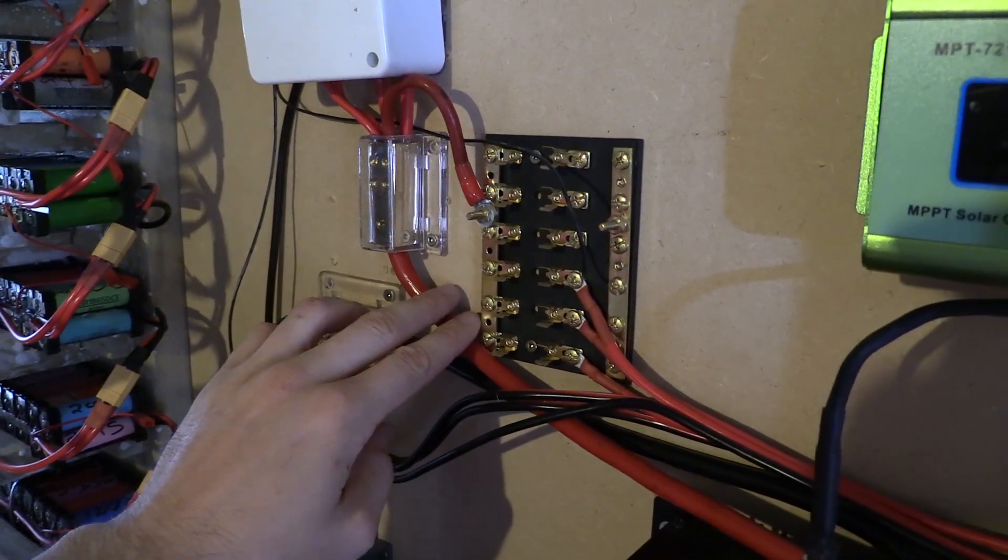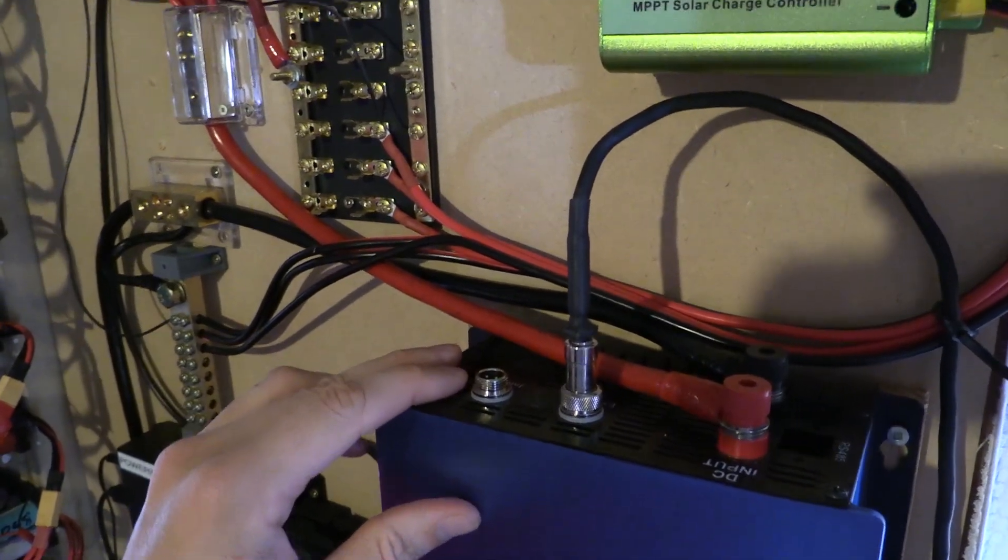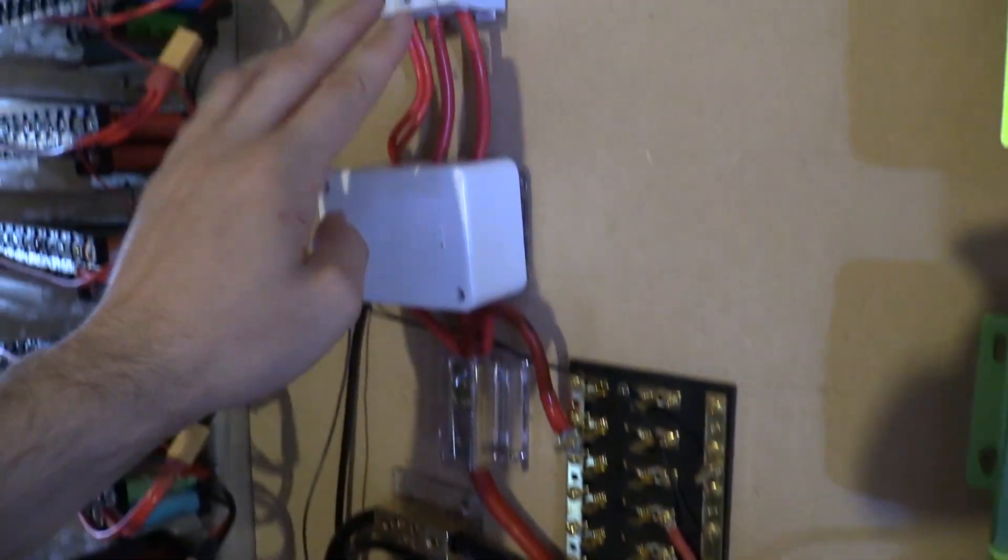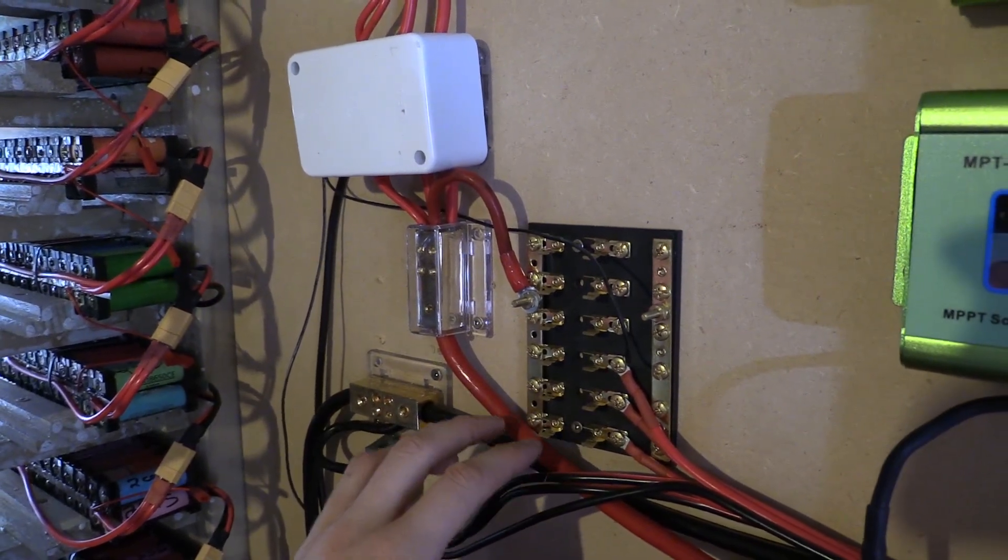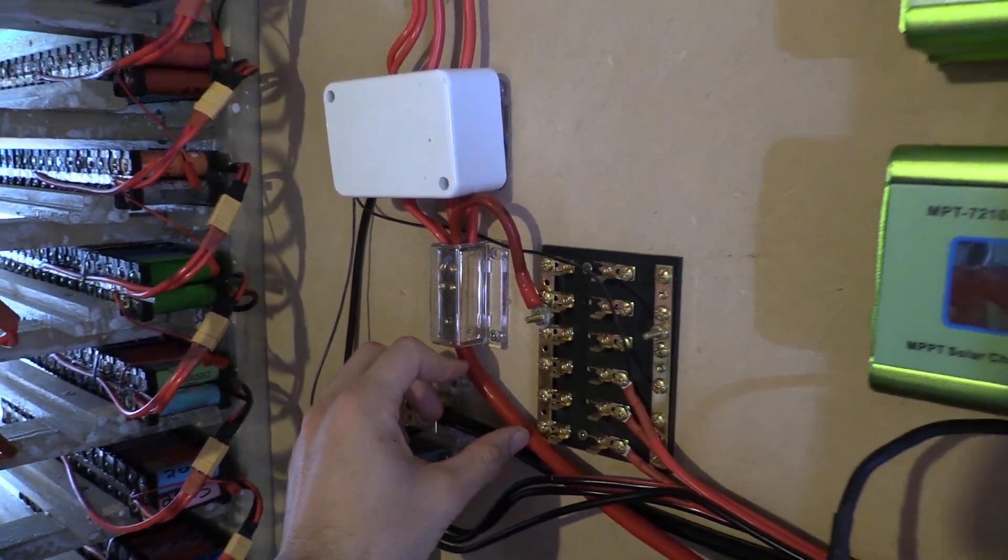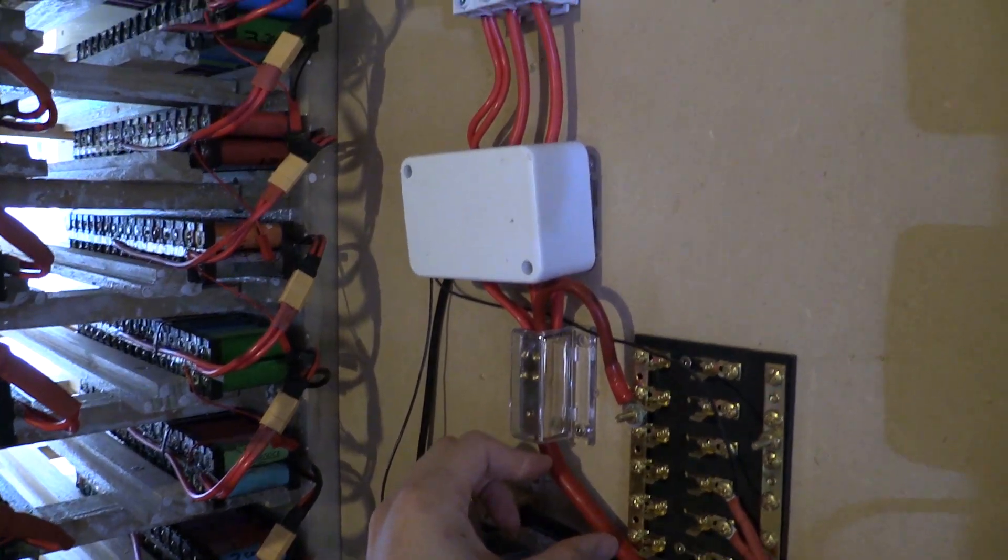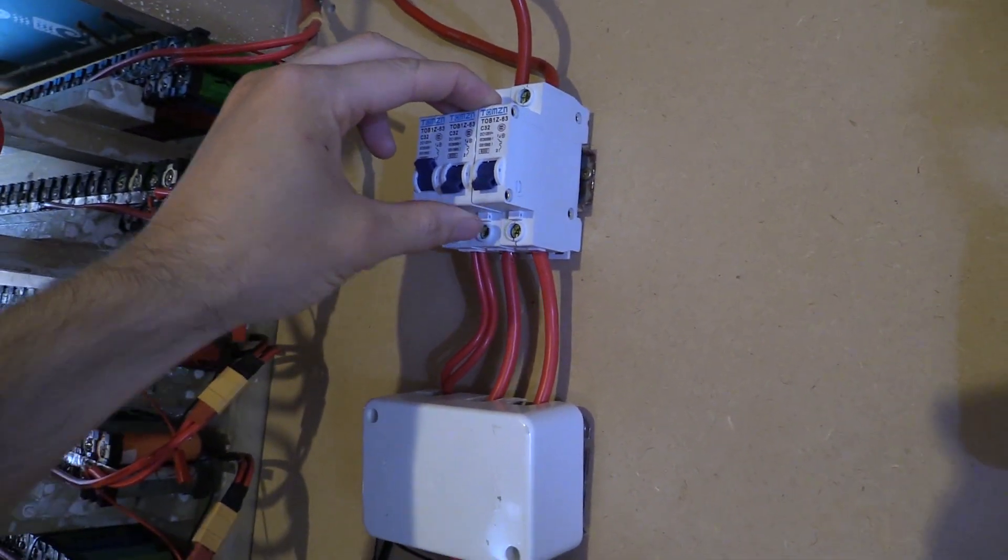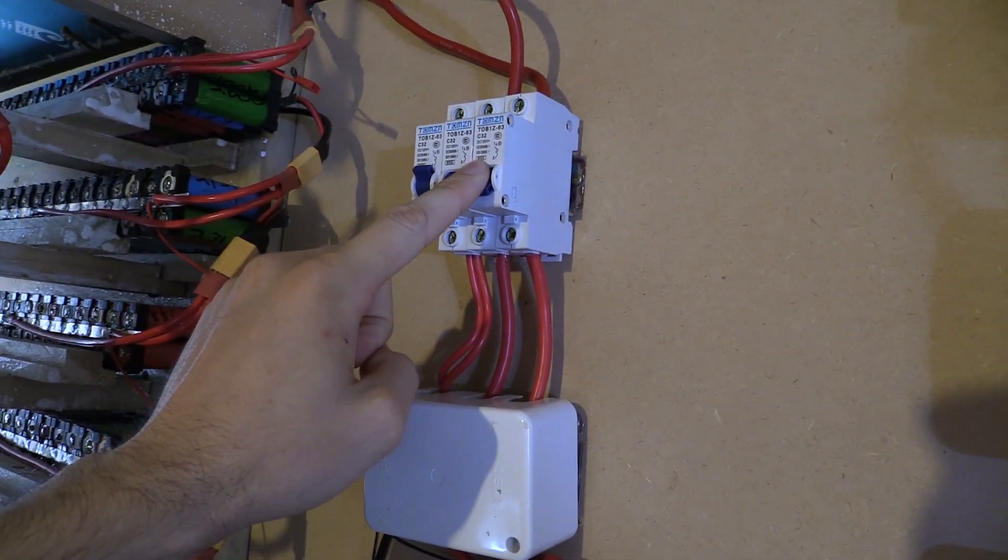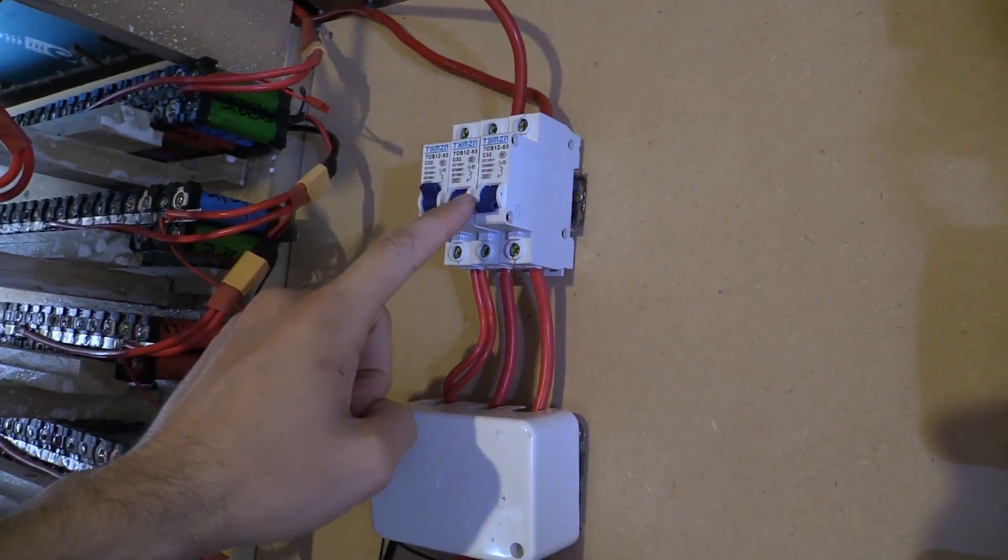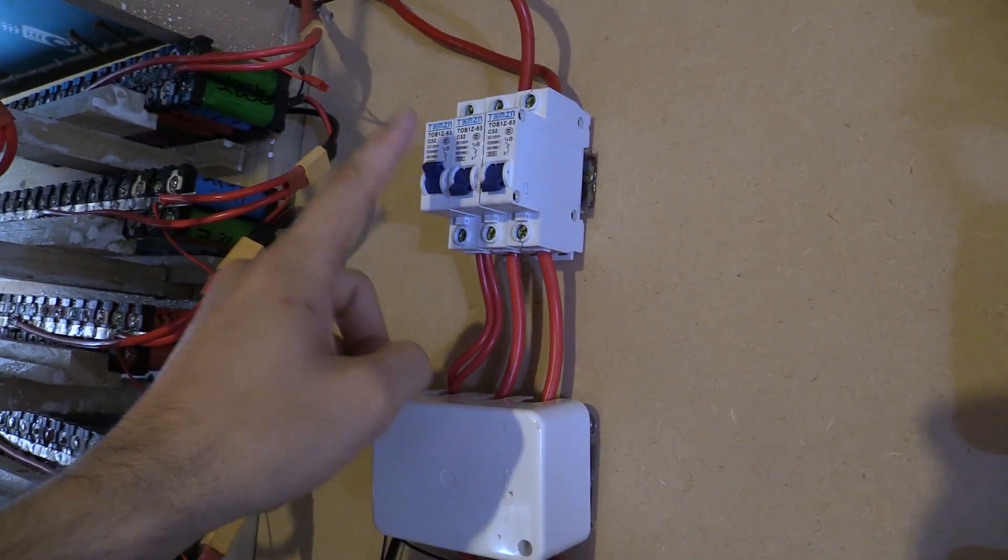What I possibly should have had was a 32, or maybe this pulls 32 amps, so potentially I should have had a 40 amp fuse or breaker on the feed into the inverter. That way that's the thing that would have blown, not these ones, and it would have meant that it would have been far easier to diagnose. That way I'd be able to see a 32 amp or a 40 amp fuse blown here and everything else would potentially have kept on running and it wouldn't have been an issue.